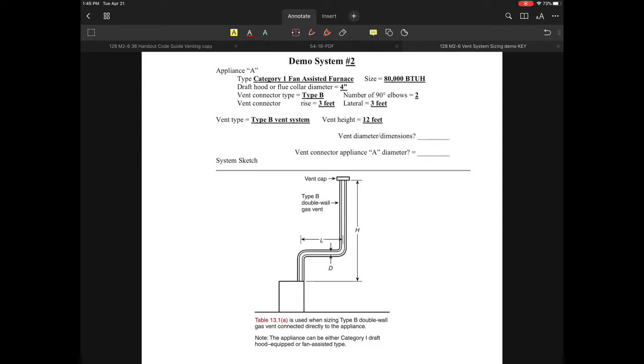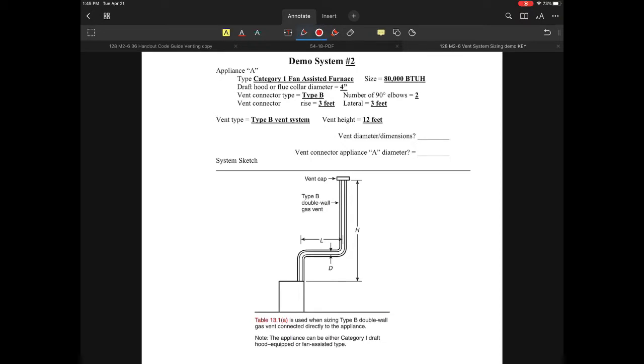This furnace has a fan at the outlet but is not a category three. The fan assists in getting gases through the appliance, but still relies on buoyancy to move gases into the vent system and out of the building. There are several appliances like this. Let's take a look at the application.